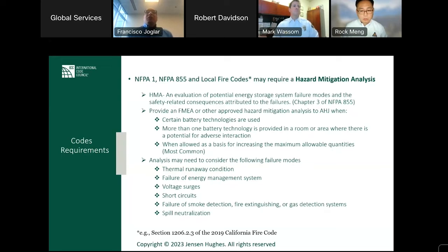in summary, what is included is failure modes that are known to generate a thermal runaway, and we keep learning about those. Cell abuse, physical abuse. There are some known failure modes associated with plating in the contacts, but it takes a simple Google search to find accidents that are reported publicly that are because there was a fire outside the batteries and heat up the batteries, and that leads to thermal runaway. I have read events where there is a sprinkler system that leaks and water is a factor in thermal runaway. Some of these batteries have liquid cooling systems. Sometimes that leaks also. So there are a number of internal and external potential failure modes that we identify in these reports.